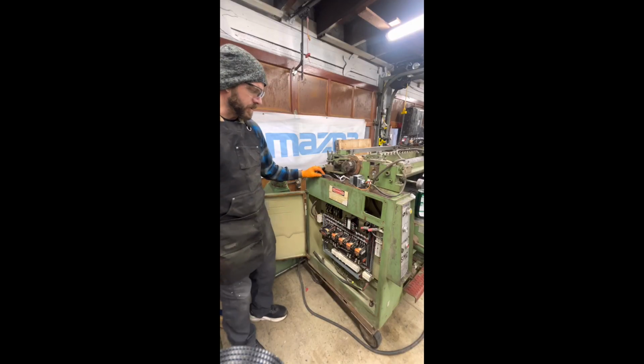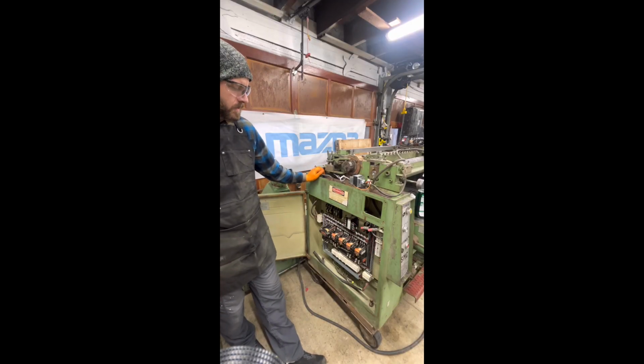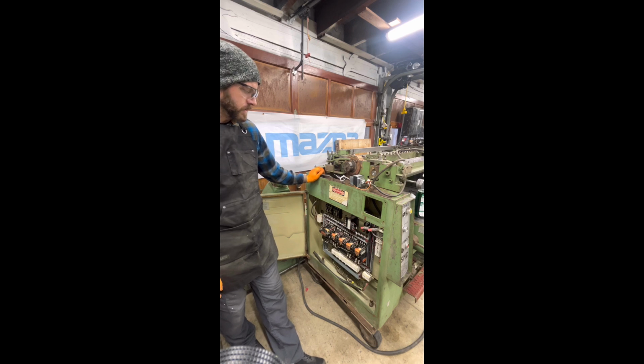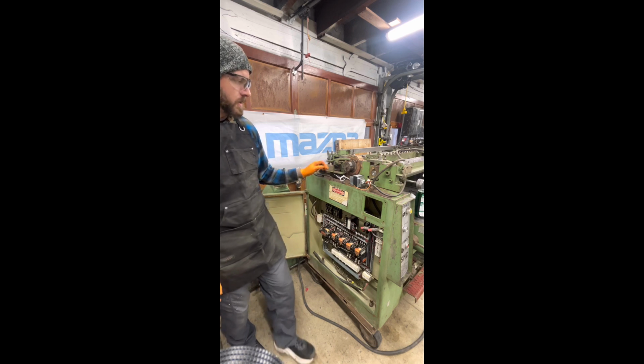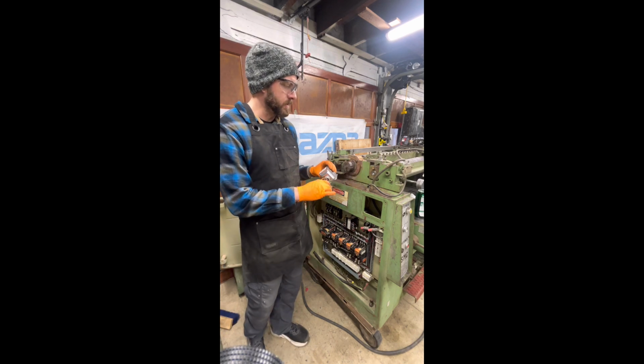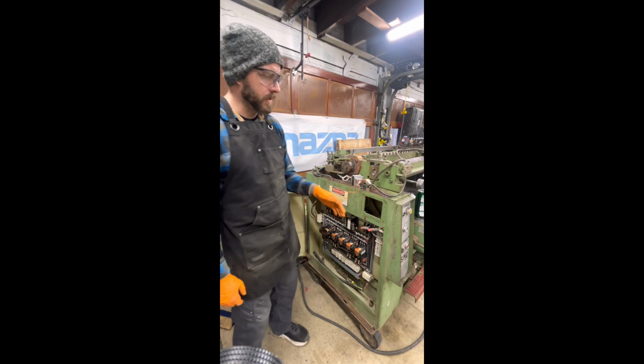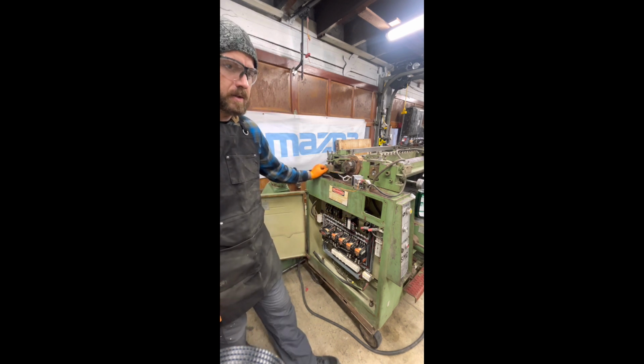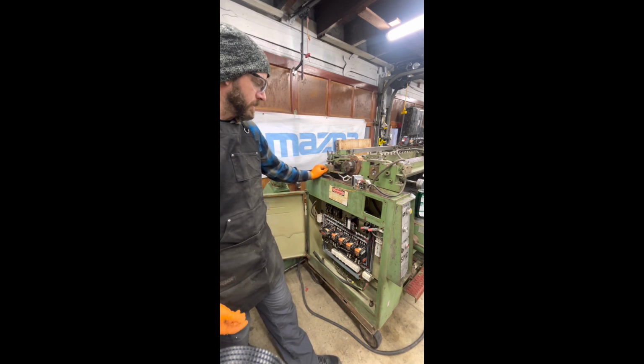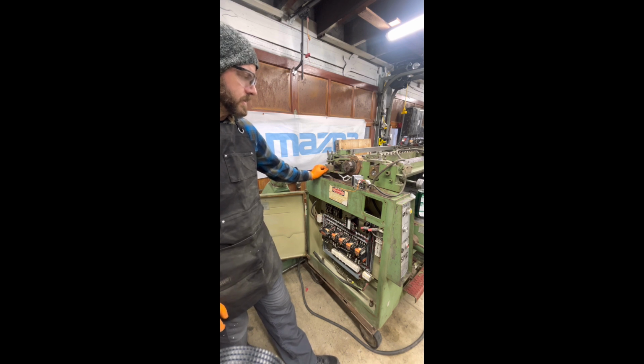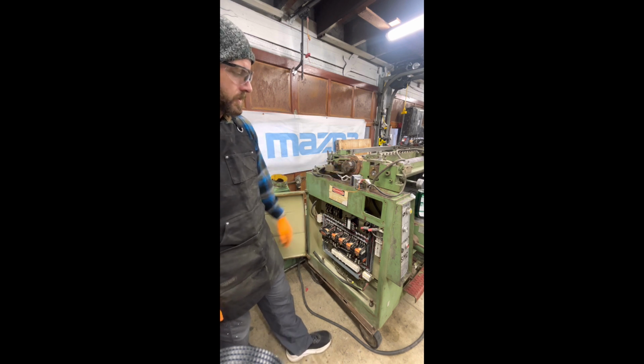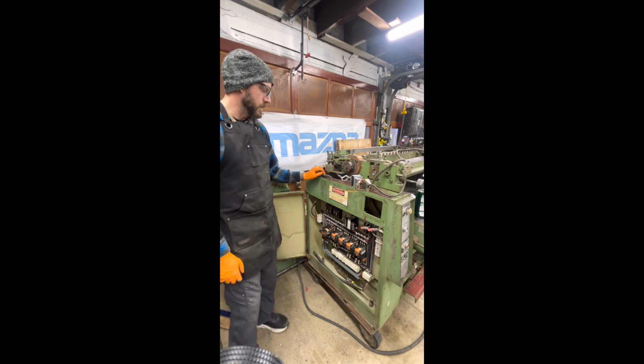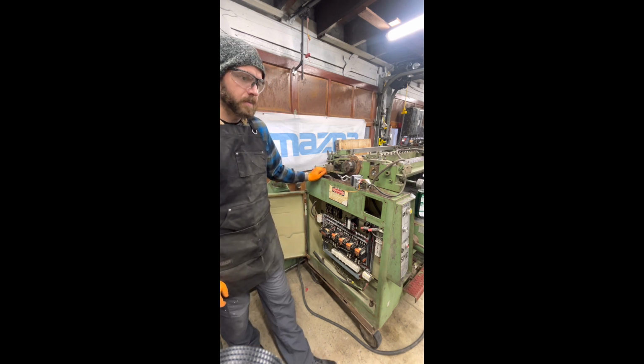So I'm going through the electrical system on this unit. When I got it from the original owner, they were having issues with the transformer that they had installed, not being able to operate the start and stop buttons correctly. It just didn't have the correct wiring, and it's not the correct type of transformer to use on a control circuit system. So this unit is designed for 230 and 440 three-phase.